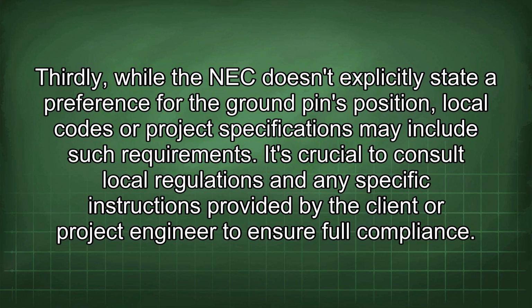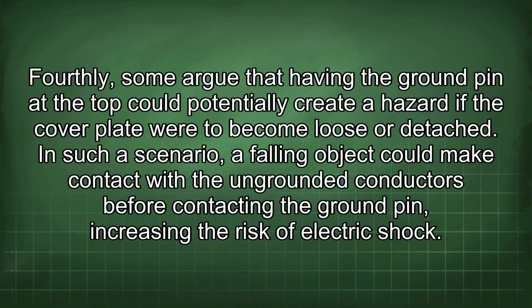to ensure full compliance. Fourthly, some argue that having the ground pin at the top could potentially create a hazard if the cover plate were to become loose or detached. In such a scenario, a falling object could make contact with the ungrounded conductors before contacting the ground pin, increasing the risk of electric shock.